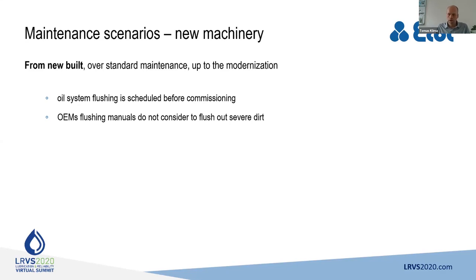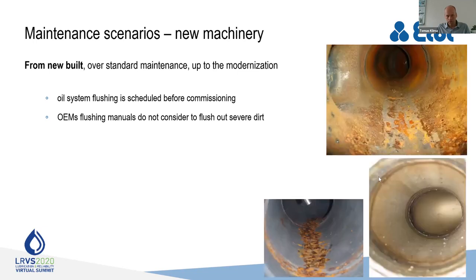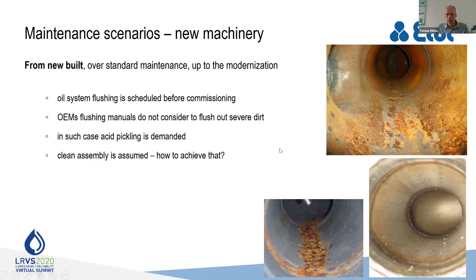Some of the systems are flushed in the workshop. However, the interconnecting pipes usually are built on site. And you can meet such projects where the pipes are corroded, dirty from the welding, from the machining. In such cases, pickling is usually demanded or other intensive cleaning. Clean assembly is assumed. However, how do you achieve clean assembly on site where all the construction is going on: cutting, machining, concrete building, and other isolation works, etc.